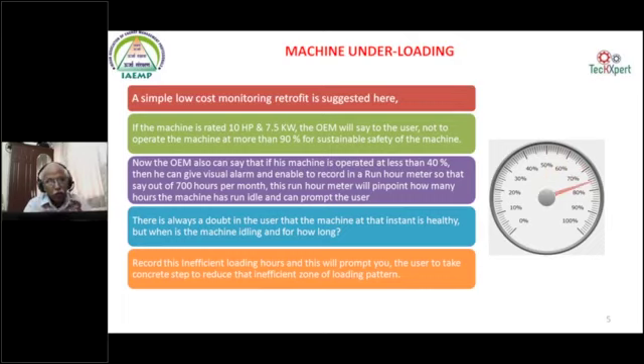There are two ways of thinking about it, because thanks to IoT, which has come in a big way now. It has come at an affordable low cost to the industry also. MSMEs have started taking up this IoT to have minimum low cost automation for all their machines. If this average time and this average kWh are known, then we know whether the motor is always running at less than 40%, whether the motor needs to be replaced, what can be done on underloaded motors, what can be done on normally loaded motors, and what can be done on overloaded motors.